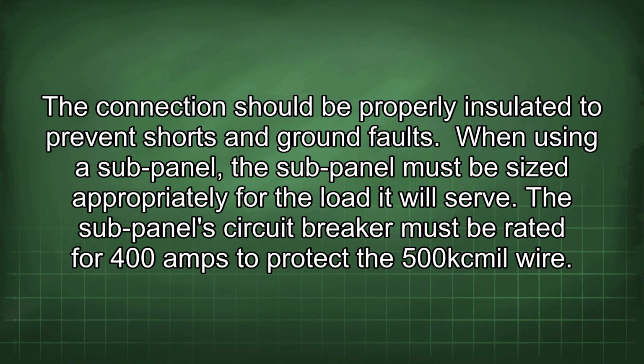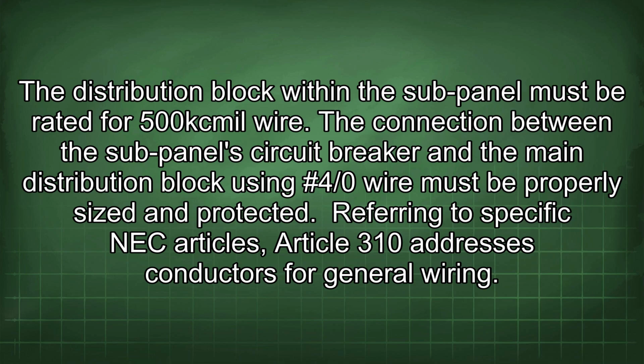When using a sub-panel, the sub-panel must be sized appropriately for the load it will serve. The sub-panel's circuit breaker must be rated for 400 amps to protect the 500 kcmil wire. The distribution block within the sub-panel must be rated for 500 kcmil wire. The connection between the sub-panel circuit breaker and the main distribution block using #4/0 wire must be properly sized and protected.